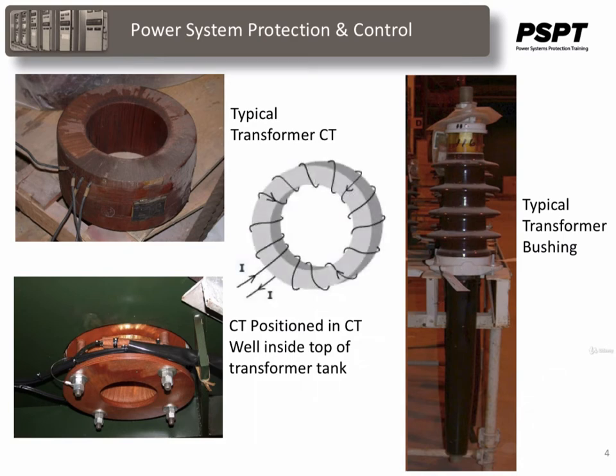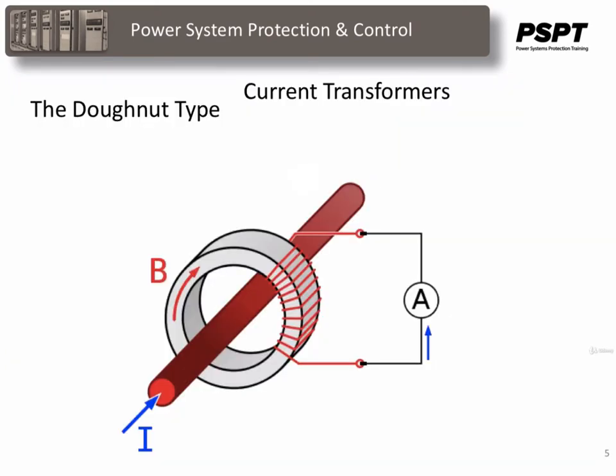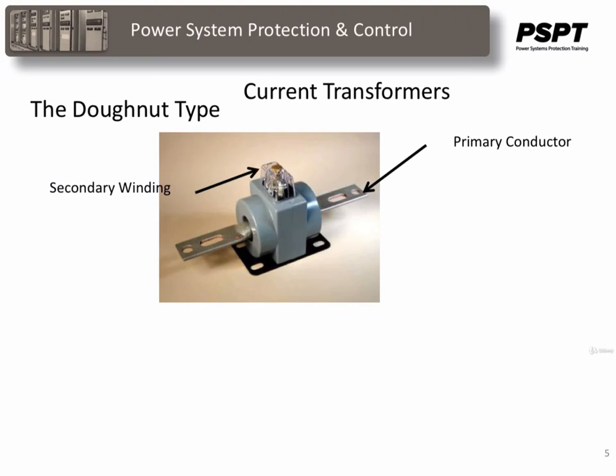The secondary winding is wrapped concentrically around a toroid, which is usually made up of laminated iron or steel. The primary is a single conductor, usually a bushing mounted through the center of the toroid. The donut fits over the primary conductor, which constitutes one primary turn. The secondary is wound around the toroid core, which is usually made up of laminated iron that concentrates the magnetic flux and forces it through the secondary turns. Some donut CTs come with the primary conductor incorporated in the CT, as you see here.